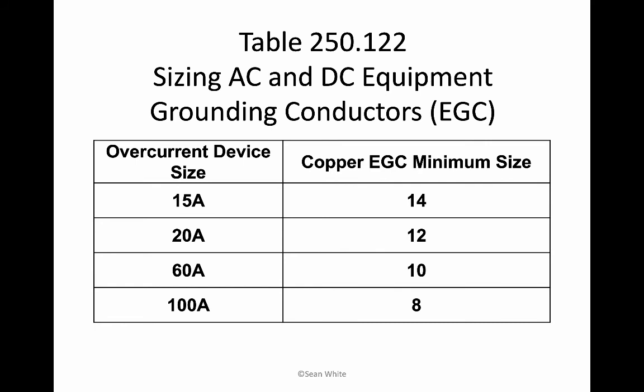But it would be compliant with the National Electrical Code. Most of the time you're dealing with PV source circuits, and if you are dealing with PV source circuits that are 15 amps or 20 amps as far as the overcurrent protection device size goes, to size the overcurrent protection device, as we will learn when we get to Article 690, you take the short circuit current that's written on the back of the module, and that's just for PV, you multiply times 1.56.